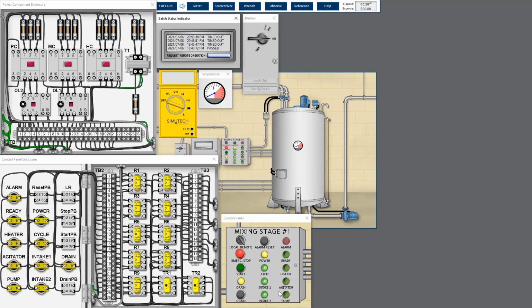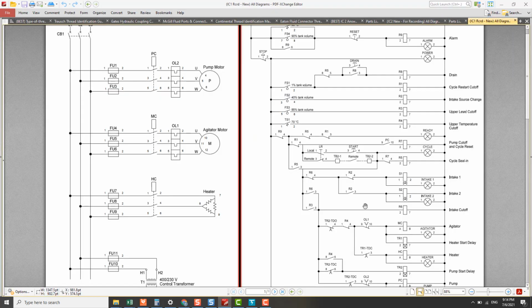However, I see one anomaly where both intake 1 and intake 2 lighting are on at the same time, which is quite abnormal. So what is the issue here? Usually, current can only flow through one branch of this parallel circuit, and the other will be stopped at R21. Now what we saw here is both intake 1 and intake 2 lighting on at the same time, but S1 and S2 solenoid valve coils did not energize and no water was charged into the tank.